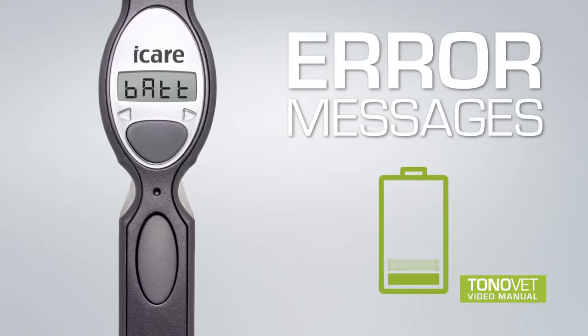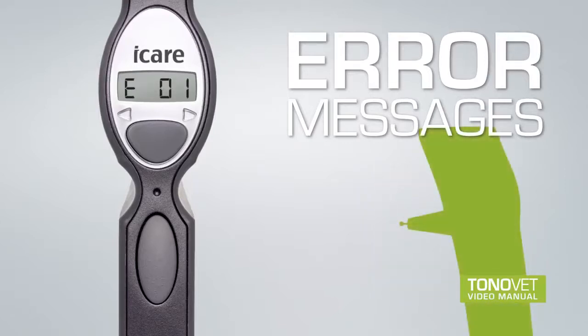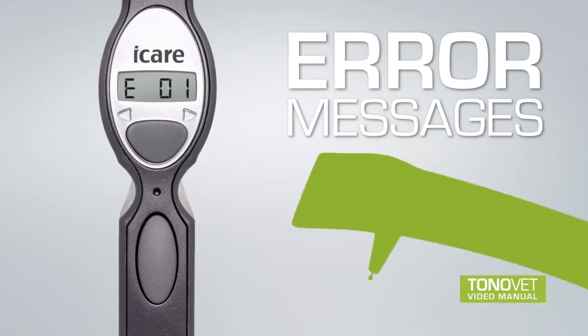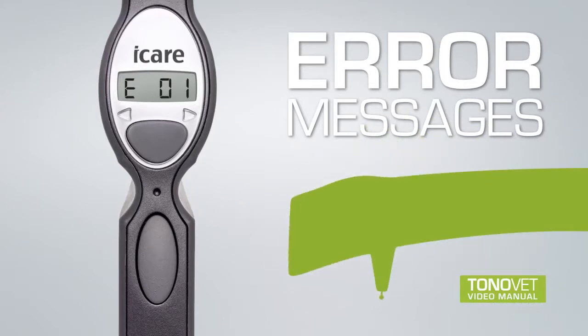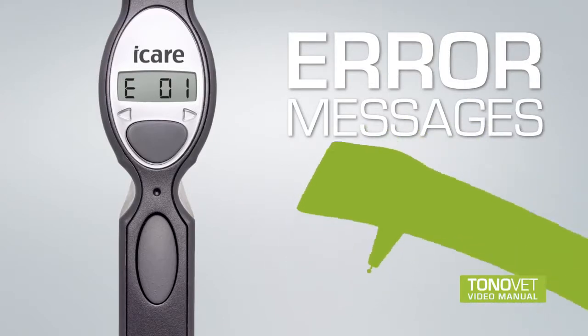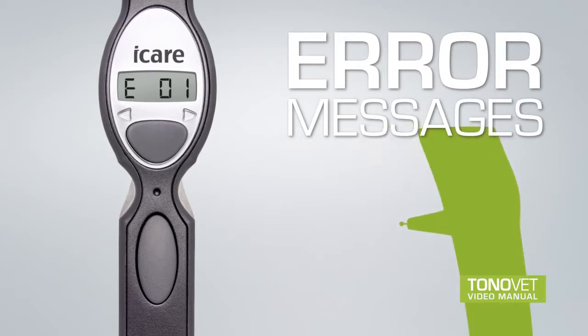BATT indicates that batteries are low and should be replaced. E01 indicates that the probe did not move at all. If this error message is repeated, turn the tonometer so that the collar faces down for a moment. If the error message is still repeated, take out the probe and replace it with a new one. If this error message continues to appear, replace the probe base with a clean one.